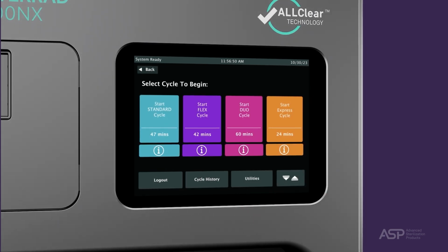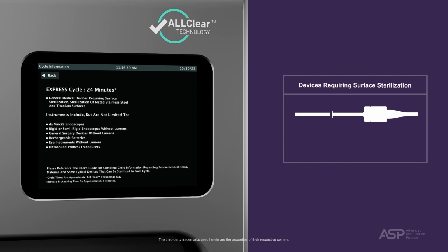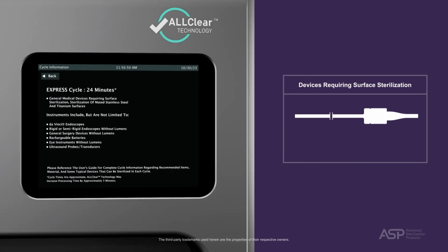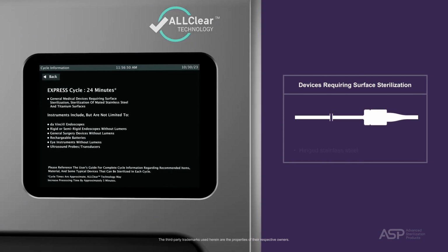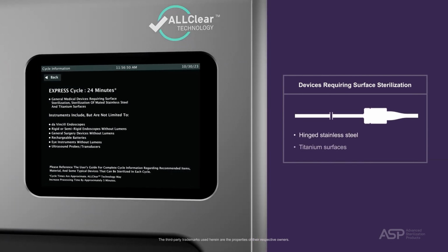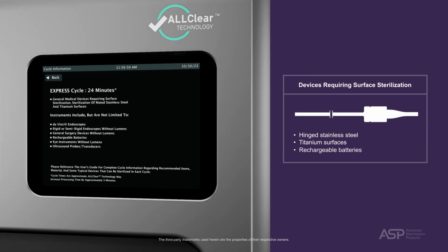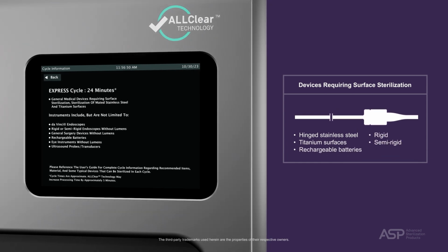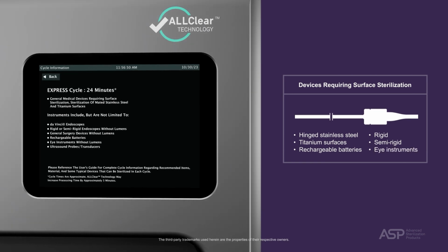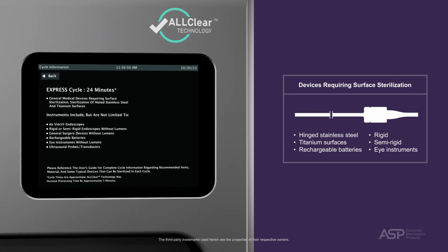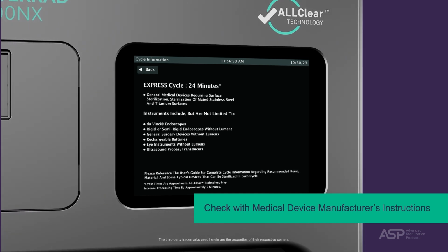The express cycle is 24 minutes and should be selected for general medical devices requiring surface sterilization or sterilization of instruments with hinged stainless steel and titanium surfaces, rechargeable batteries, and non-lumen rigid or semi-rigid endoscopes, eye instruments, and general surgery devices, such as Da Vinci 3D endoscopes. Check with the medical device manufacturer's instructions when selecting the proper sterilization cycle.